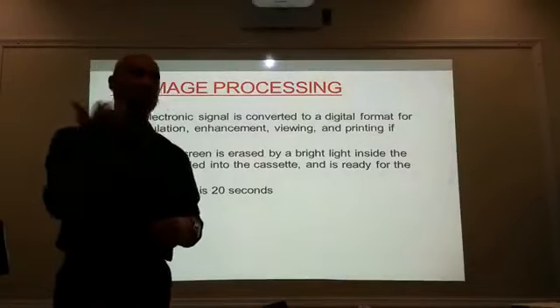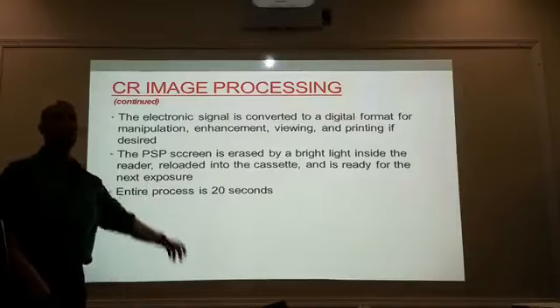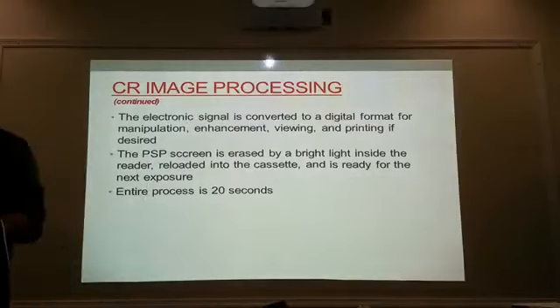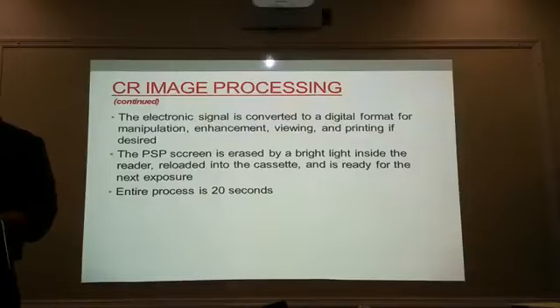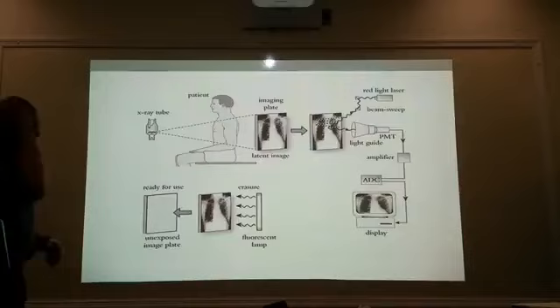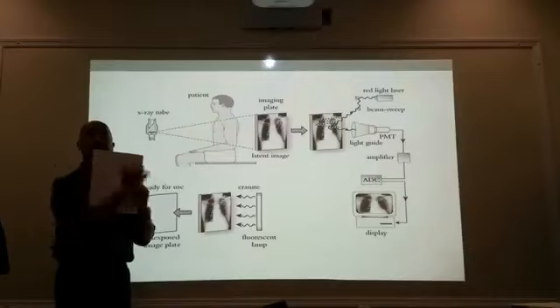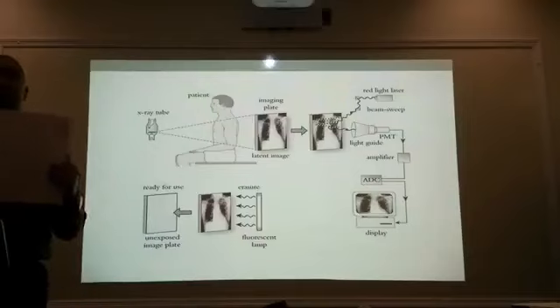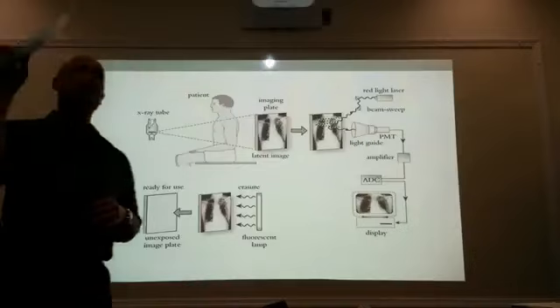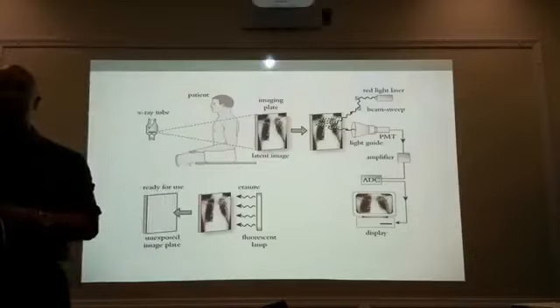Unlike film — if you put film under light, it gets exposed. With the PSP, we're actually using light to erase our screen to be used again. After the image is extracted, the PSP gets scanned with a very intense white light to remove the remaining energies from the crystals so the screen can be used 10,000 times over.